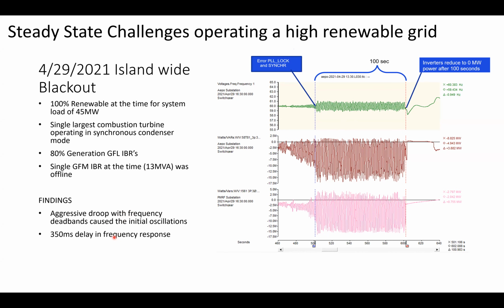And the other lesson learned is the inverter-based fast frequency response on some of our systems was only playing a portion into the droop response. Another portion of it was a plant controller also operating in droop to help provide a slower speed droop response, and that was 350 milliseconds. We found that to be a little bit too slow for us, and so we've since had that removed, and our fast frequency response at 50 milliseconds is our true droop response right now.